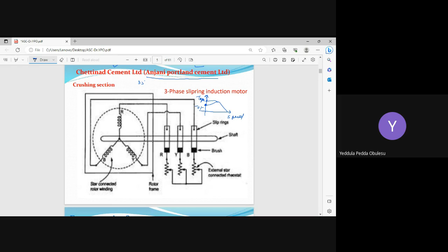To increase the starting torque, the conventional way was used, because this Anjani Portland cement plant is 35 years old. We carried out this study for the existing cement plant. There they used the slip ring induction motor by inserting external resistance into the rotor circuit, with the help of brushes and slip rings, to increase the starting torque to crush the raw material to the required levels.